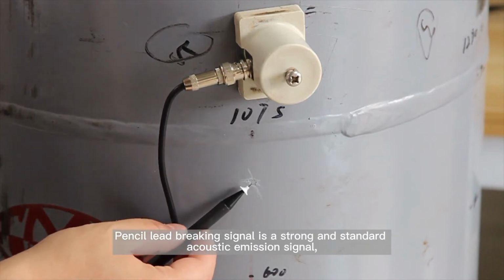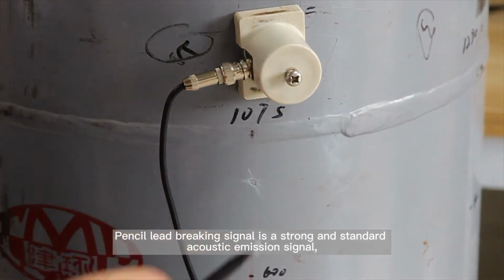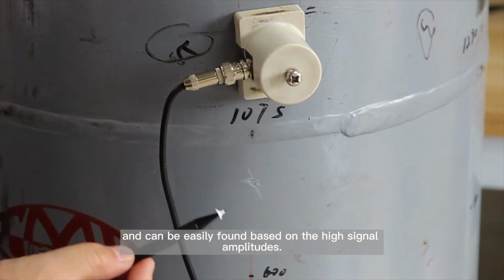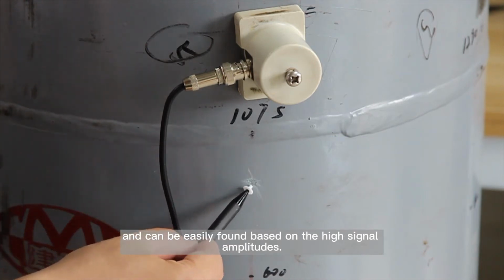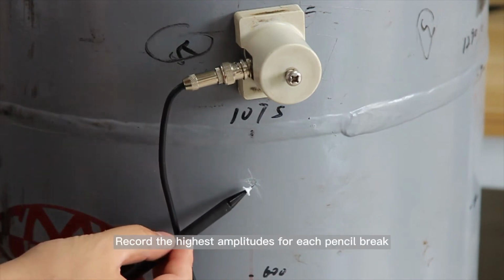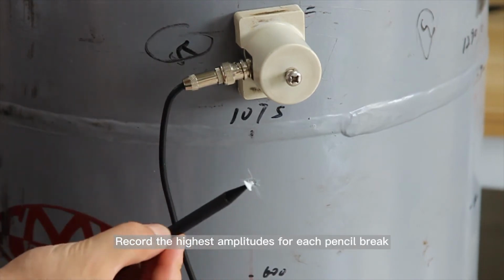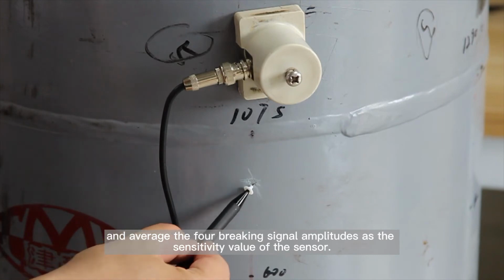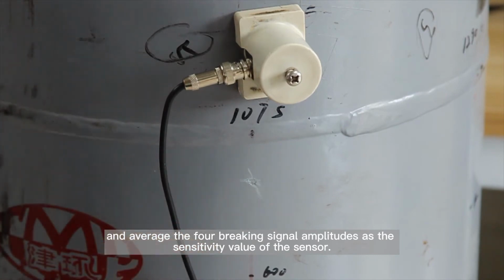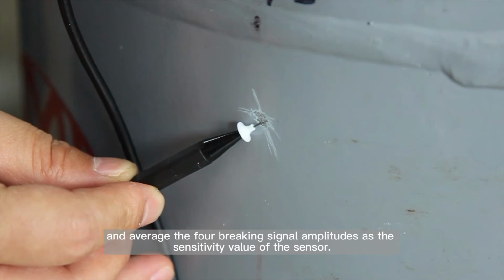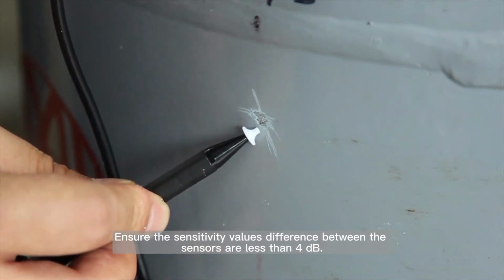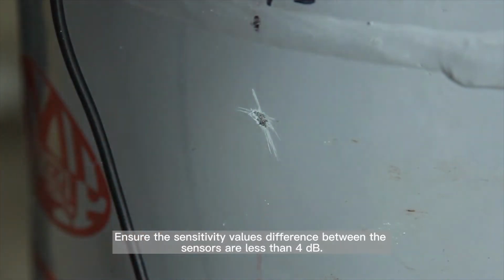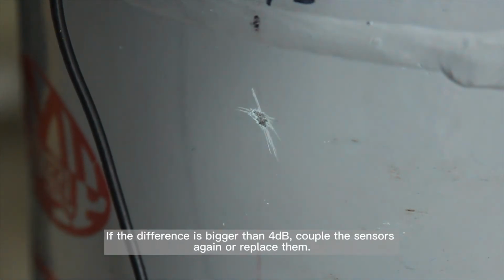Pencil lead breaking signal is a strong and standard acoustic emission signal and can be easily found based on the high signal amplitudes. Record the highest amplitudes for each pencil break and average the 4 breaking signal amplitudes as the sensitivity value of the sensor. Ensure the sensitivity values difference between the sensors are less than 4 dB. If the difference is bigger than 4 dB, couple the sensors again or replace them.